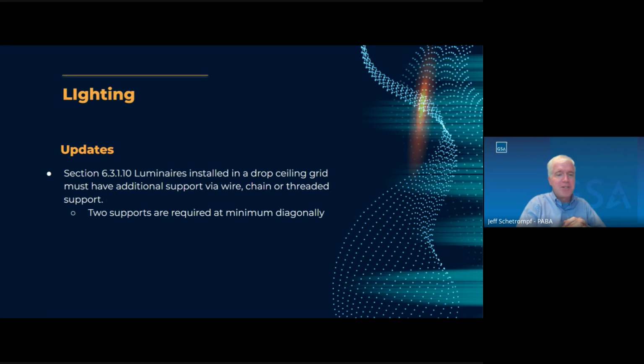So we're going to do a little pause and see if there's any questions on lighting before we go on to power. Yeah, we do have one question from Mark in the Q&A. It says, does the project AE have to change the standard electrical specification to require red cabling for emergency lighting? And I would say yes. And typically what we've seen is that the non-emergency lighting would be maybe a yellow cabling, and then your comm cabling is typically blue.